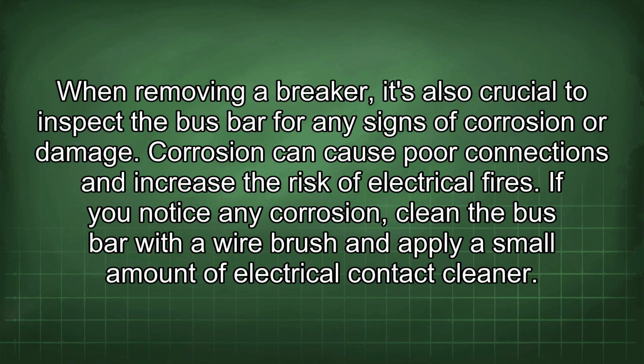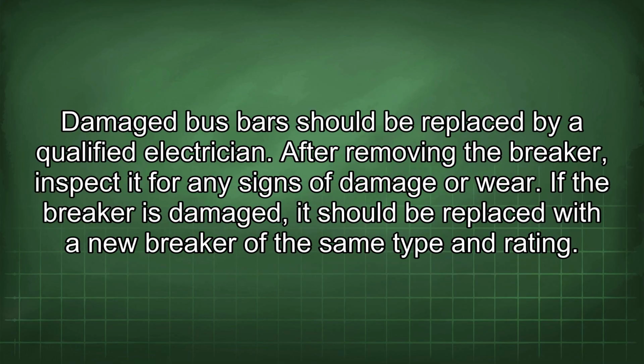When removing a breaker, it's also crucial to inspect the bus bar for any signs of corrosion or damage. Corrosion can cause poor connections and increase the risk of electrical fires. If you notice any corrosion, clean the bus bar with a wire brush and apply a small amount of electrical contact cleaner. A damaged bus bar should be replaced by a qualified electrician.